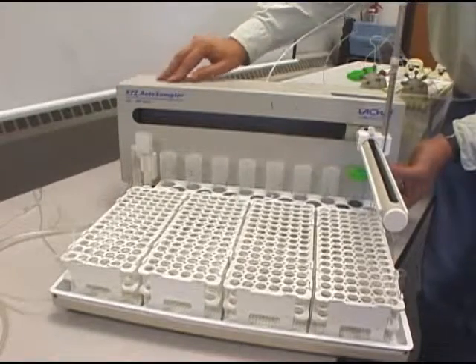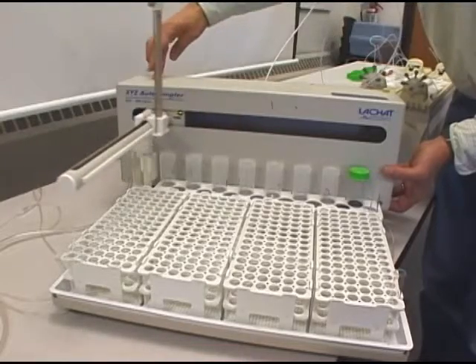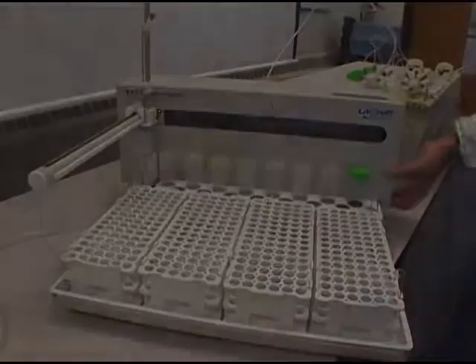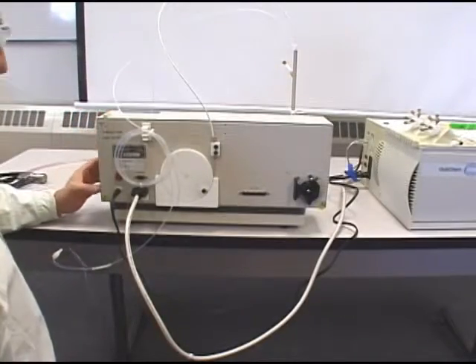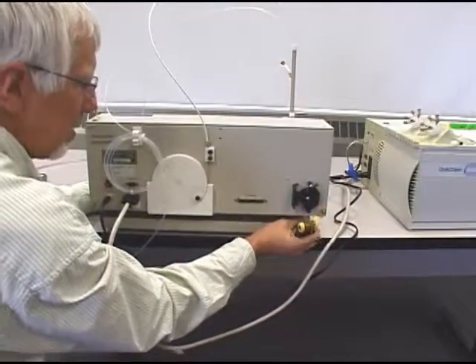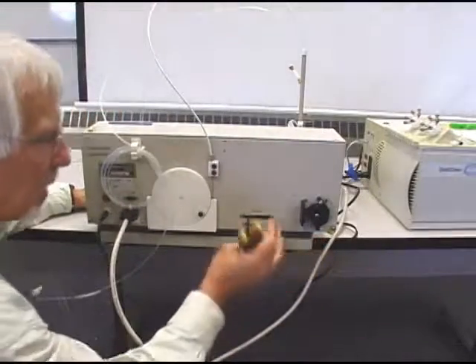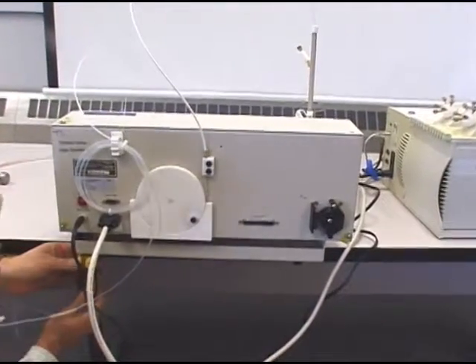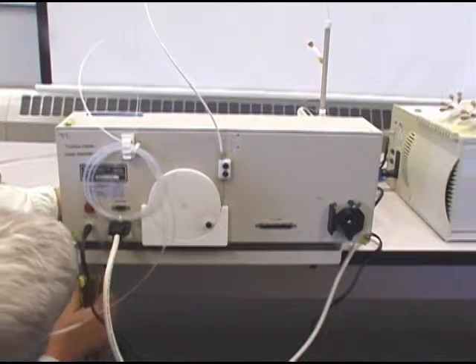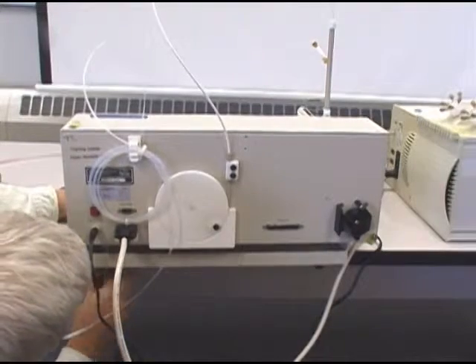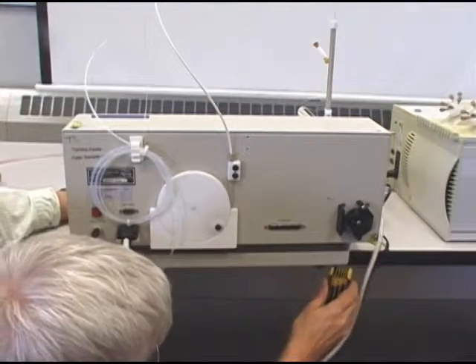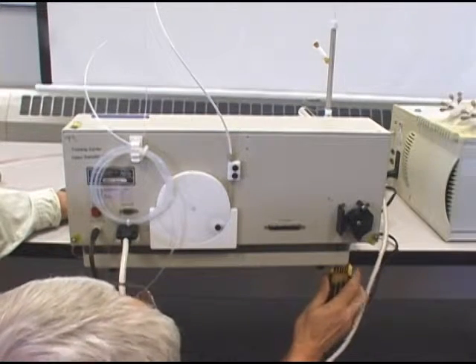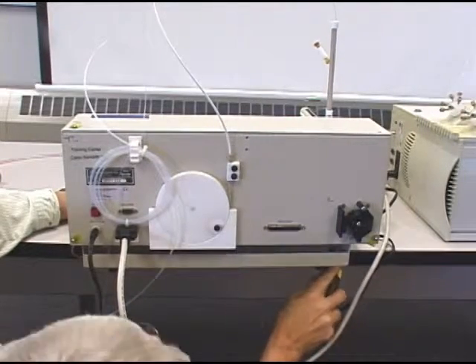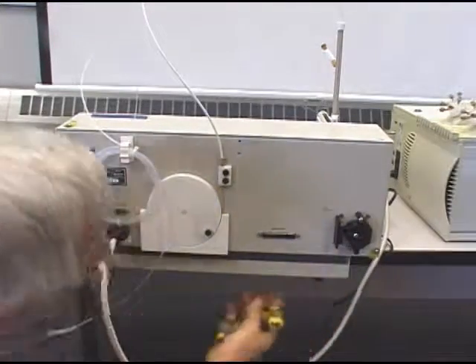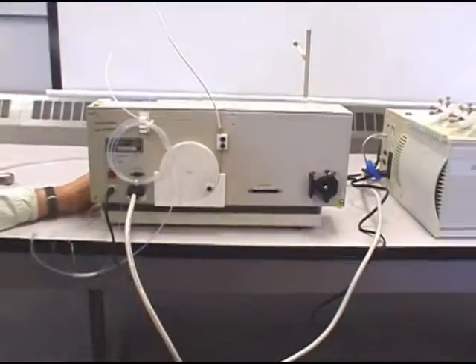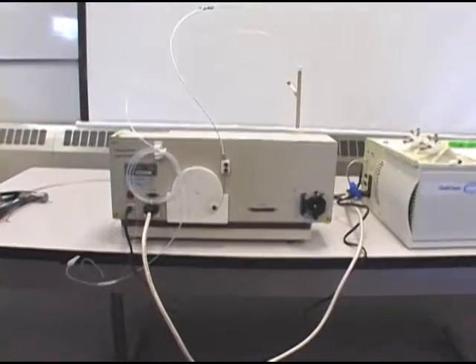So now what I need to do, once this program is stopped, is go back and carefully tighten those screws without moving the carriage from the tray. Once we've got the auto samplers positioned on the sample cups fixed, we want to very carefully slide the autosampler back without moving the carriage with respect to the tray, and tighten those 4 Allen head screws. We'll then run the 4 corners test one more time to make sure the thing did not go out of misalignment, and make sure that all 4 tubes are hit squarely.